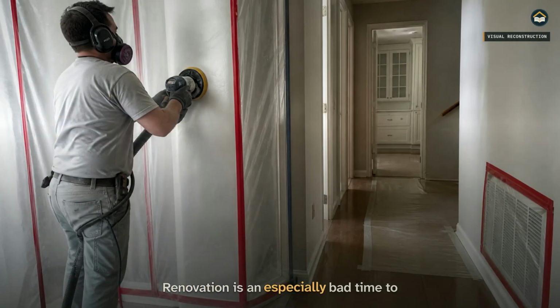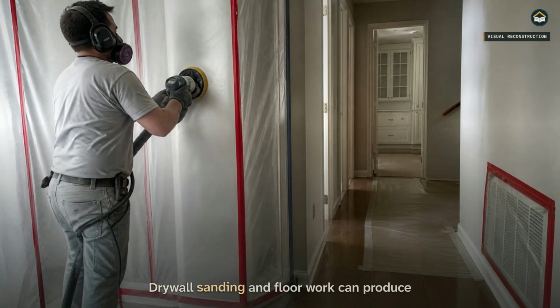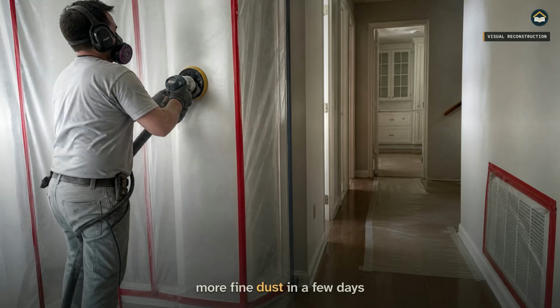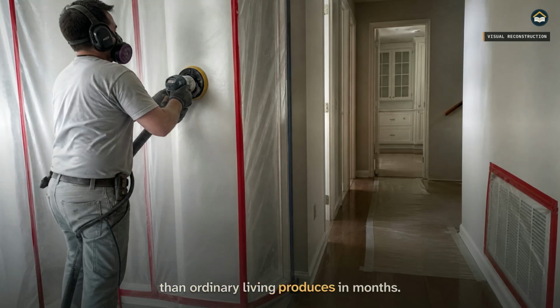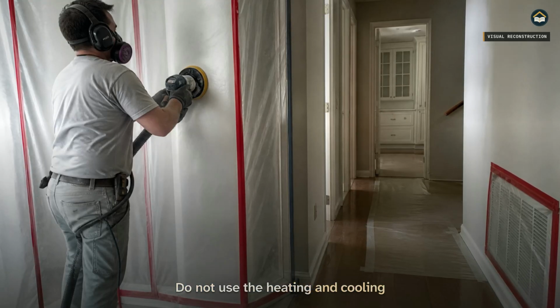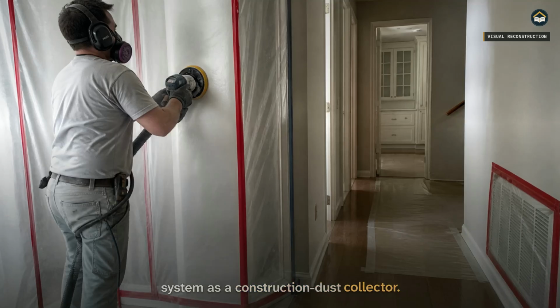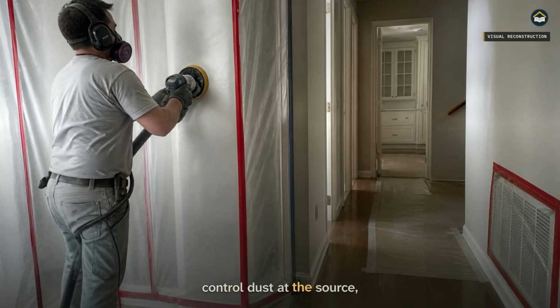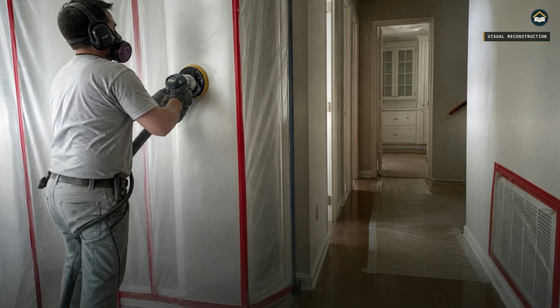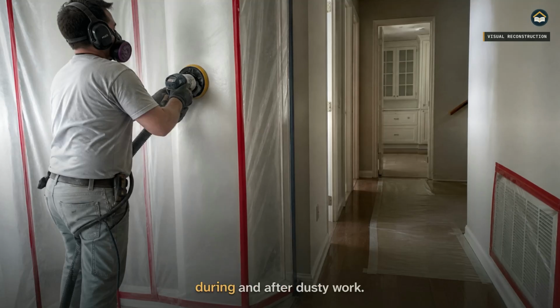Renovation is an especially bad time to forget this. Drywall sanding and floorwork can produce more fine dust in a few days than ordinary living produces in months. Do not use the heating and cooling system as a construction dust collector. Isolate the work area, control dust at the source, follow the contractor's plan, and inspect the correct filter more often during and after dusty work.